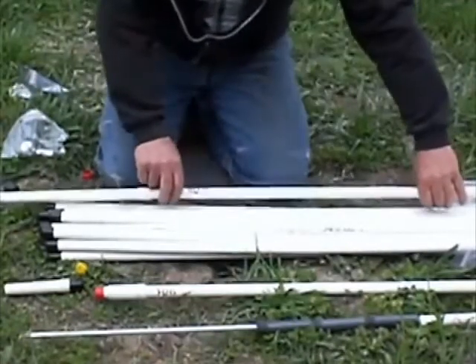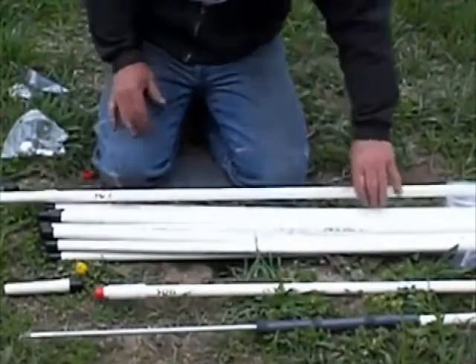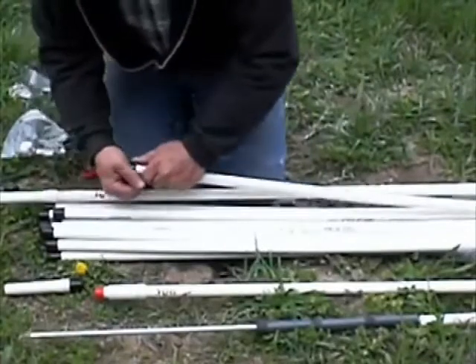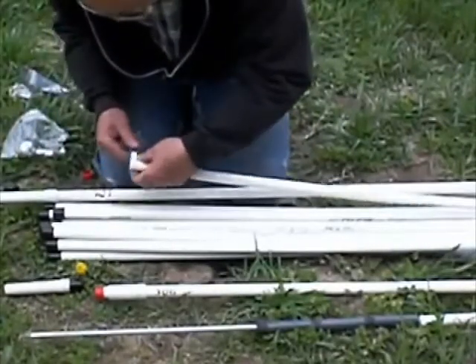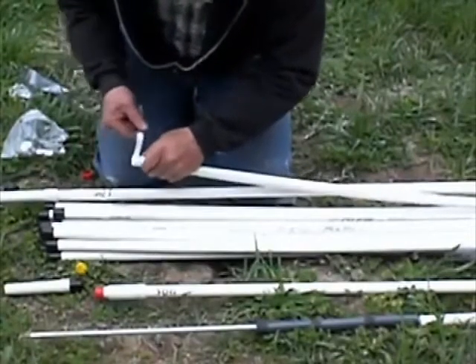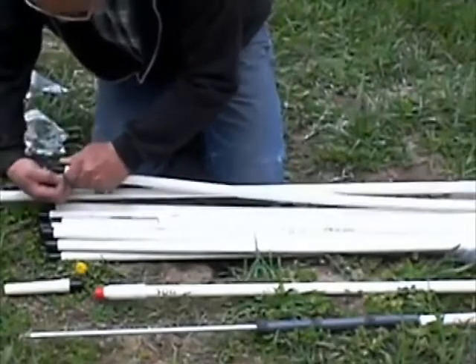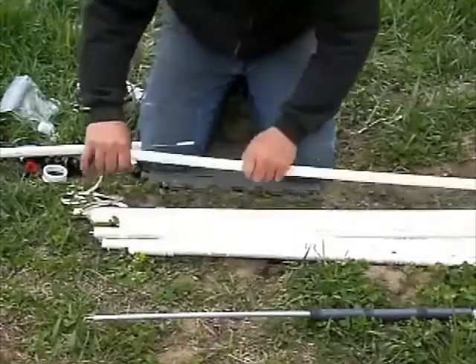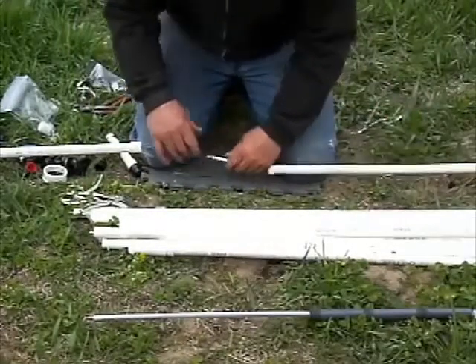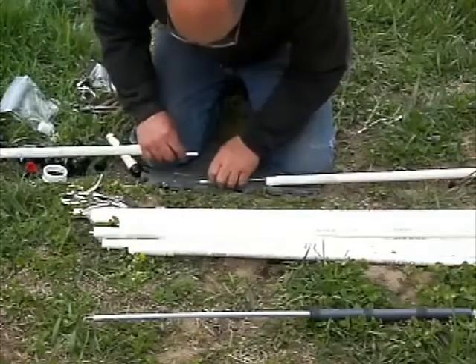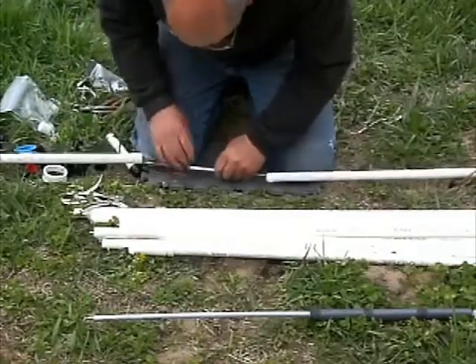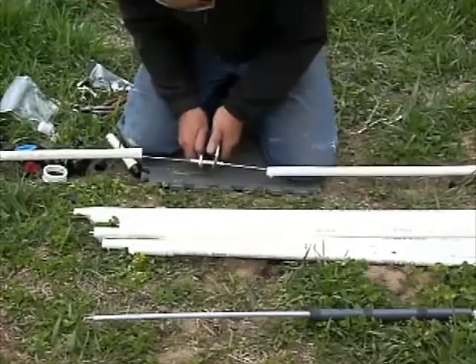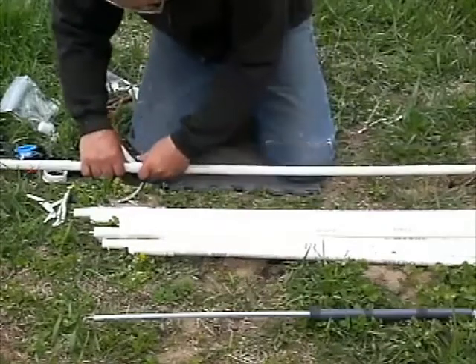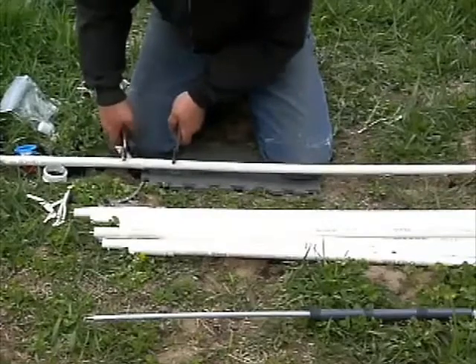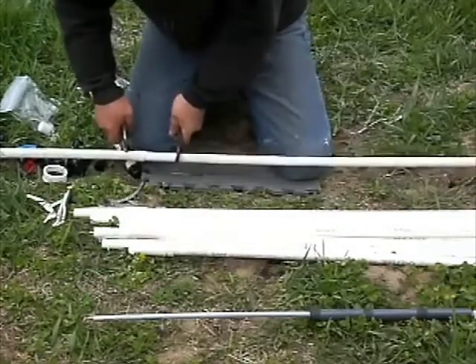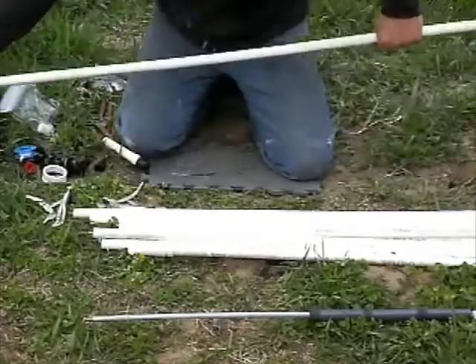The next section installed will be the center drop sections with the black caps on both ends. Remove the caps and apply Teflon tape to all the male ends. Thread the wire lift rods and pipes together as previously done. If you see small bends in the wire, you can straighten them by hand as you go. Repeat until all center drop sections are installed.